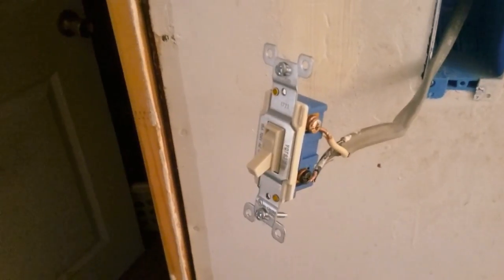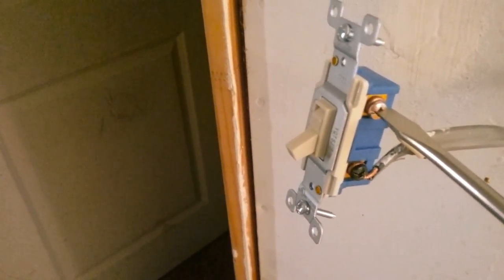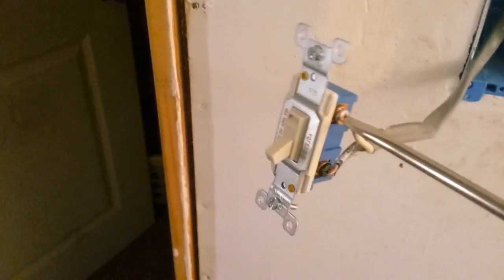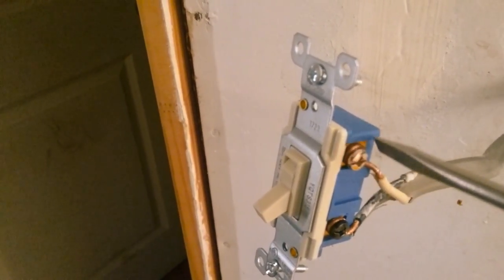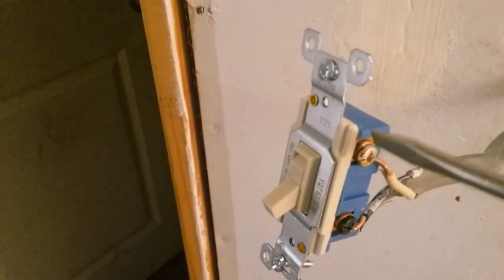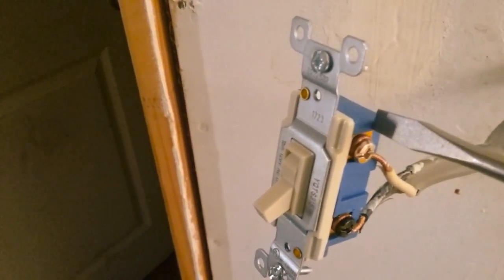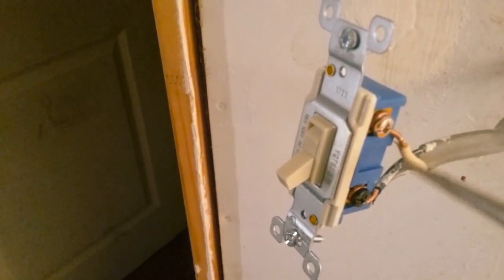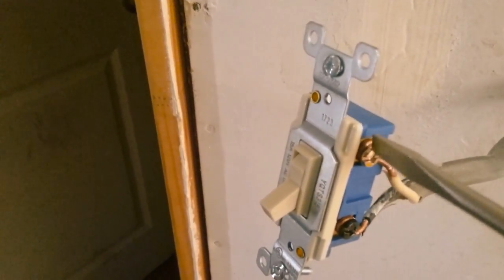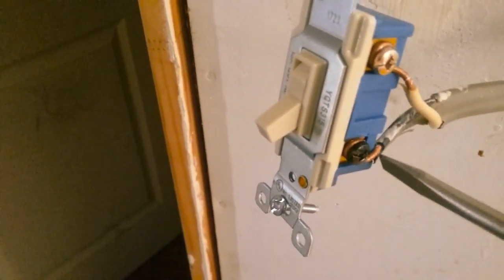Don't think much of electricians who do it, because it's just not as secure as putting a little bend in your wire and then putting it on the screw. This is a much better secure system in my opinion. I know I've seen tens of thousands over 20 some odd years. So anyway, make your hook on your wire and get it below this screw. Your hook needs to be going this way, going clockwise. So when you tighten this screw, it tightens against this wire and pulls it in the direction. Otherwise, you could be tightening it up if you went this way and your wire could be opening up and you'll not get a good contact with it. Same way here, loop comes this way, goes under and goes over, just clockwise. So anyway, there you have it.